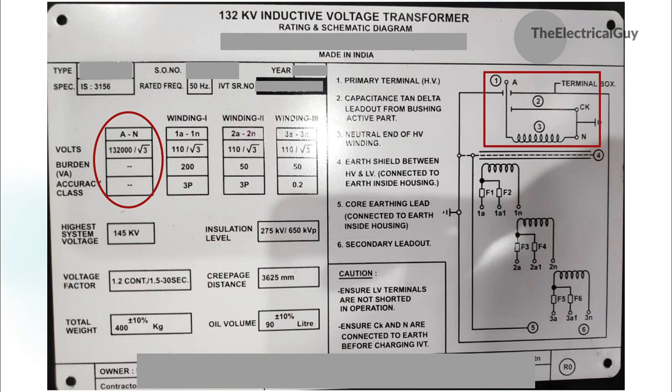Next we have the winding details of the IVT. The first column tells us about the primary side of the transformer. The first row in the first column tells us about the connection — if you look at the schematic diagram you will find letters A and N, where A is the primary connection. In the second row it says volts, mentioned as 132kV divided by root 3. Voltage transformers are connected phase to earth and hence the voltage is divided by root 3. Burden and accuracy class are not applicable for the primary winding.